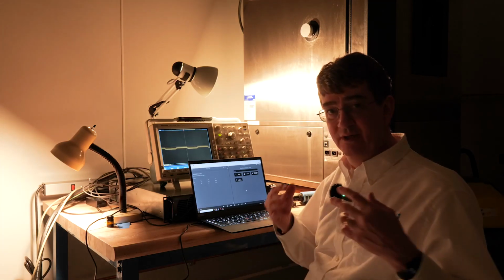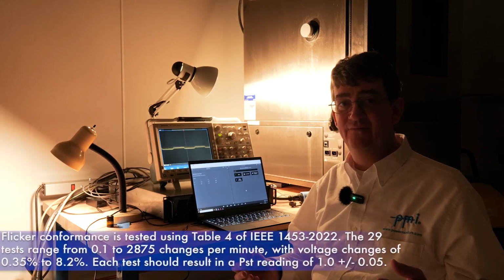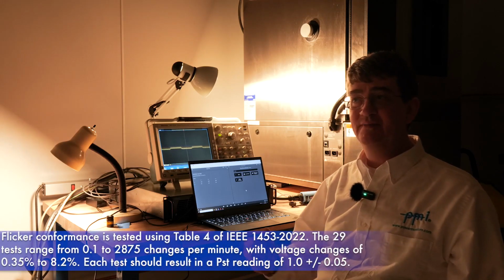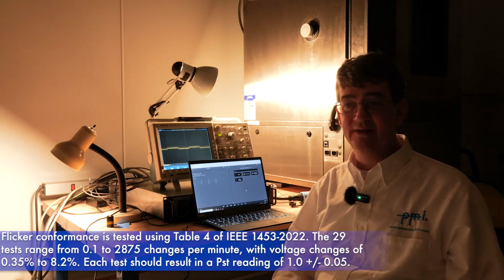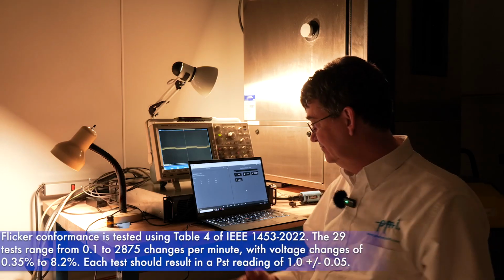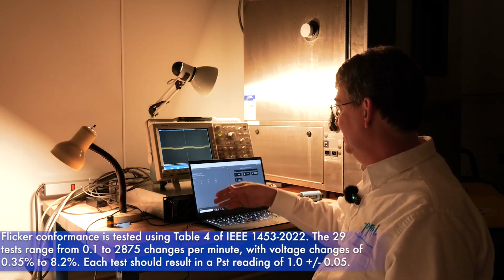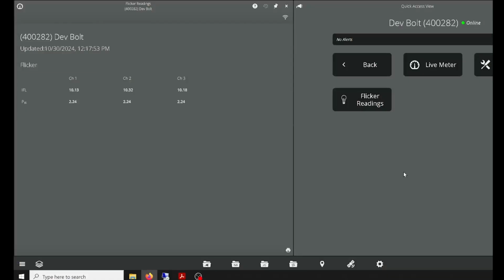And we are going to go through the conformance test that is specified in 1453 and also do some extra testing on the Bolt to make sure that the implementation is good. So here's a spot check. This should be around 2.2, and it is reading 2.2. We're using PQ Canvas to get live readings from the Bolt.